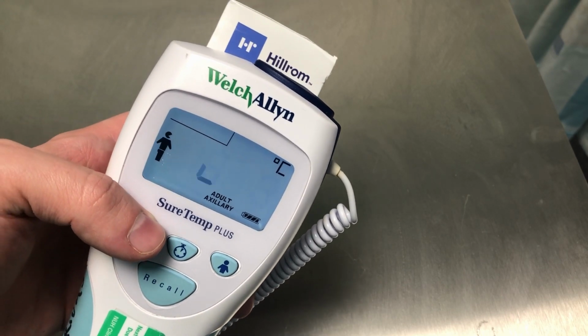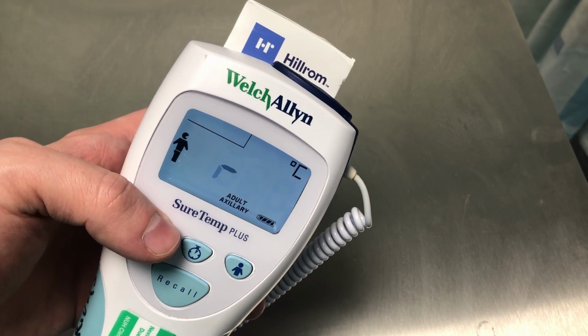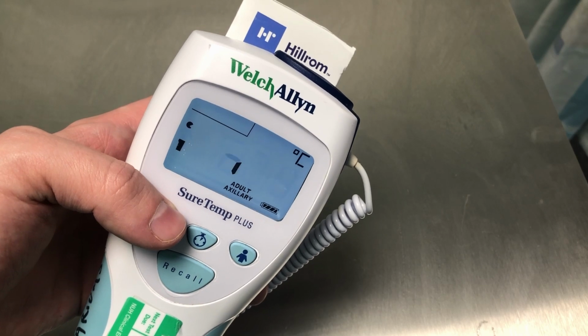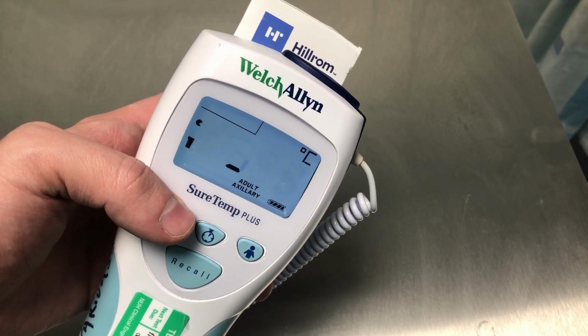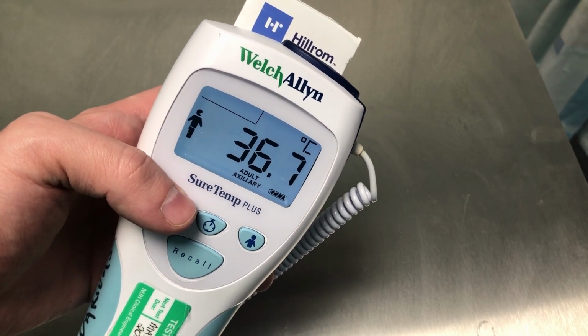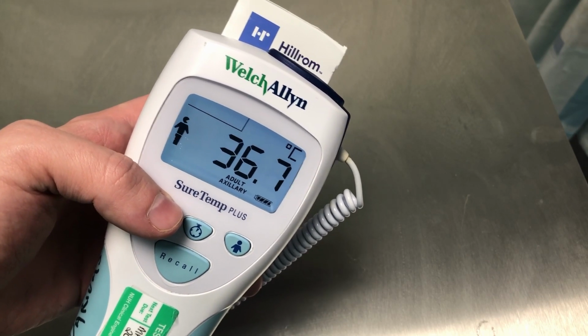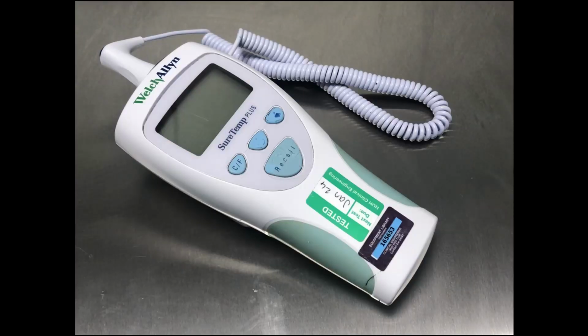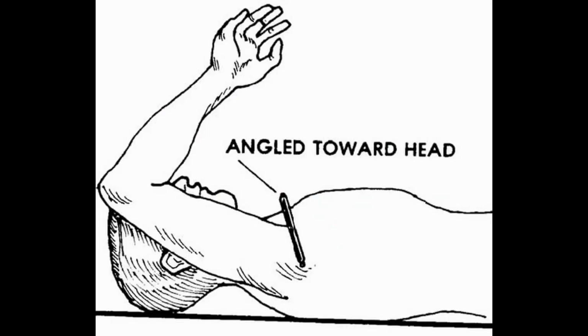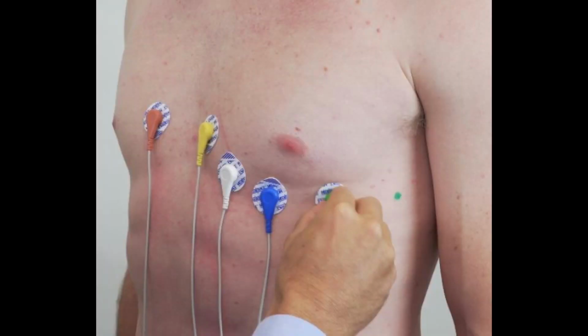Now it will do the algorithm, and that's it, just trying to work it out. And after a few seconds you should get a predicted temperature. So for axilla temperatures, there are a few things that affect them. Poor tissue contact, taking temperature through a patient's clothing, you cannot do that, probe contact with electrodes or bandages, or prolonged exposure of the axilla to ambient air.